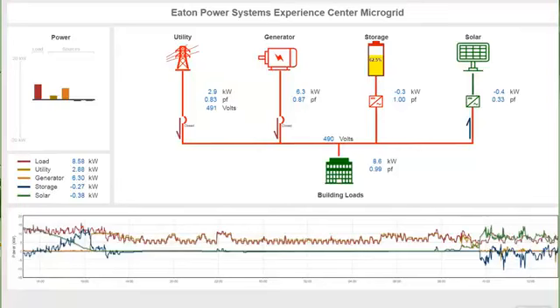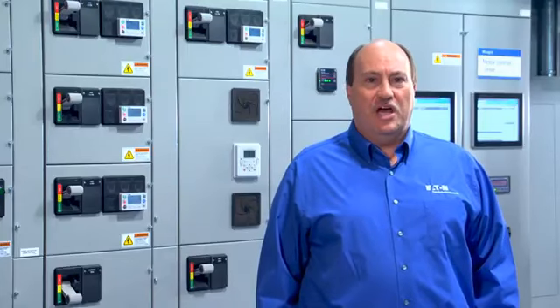In fact, this provides two levels of redundancy. If one alternate source is not available, for example, if the batteries are discharged, the next source, or the generator, is automatically selected. While in an islanded state, the microgrid maximizes the use of free solar energy. Any excess energy is stored in the batteries. If the generator is running, it also supplies loads and charges batteries, allowing the generator to be turned off for intervals while the batteries carry the load.